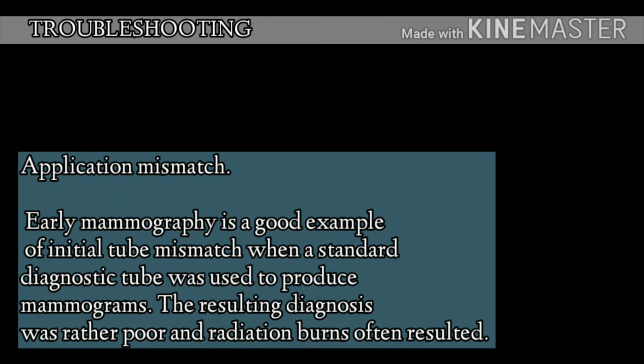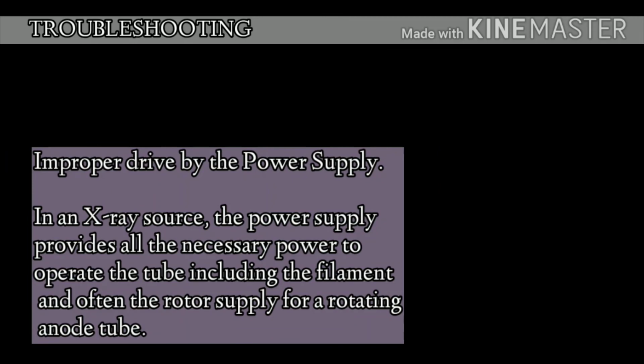Second, application mismatch. Early mammography is a good example of tube mismatch when the standard diagnostic tube was used to produce mammograms. The resulting diagnosis was rather poor and radiation burns were often the result. Lastly, improper drive by the power supply. In an X-ray source, the power supply provides all the necessary power to operate the tube, including the filament and often the rotor supply for a rotating anode tube.